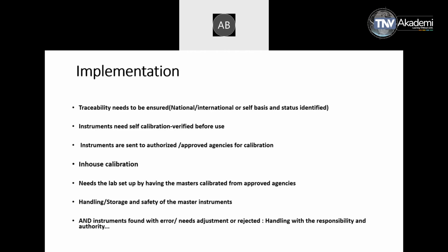Once we start doing calibration in-house, the training of the team again comes into the picture. They need to be trained to do effective, good and correct in-house calibrations of the instruments and machines. Then there is how to handle, store and keep safe the master instrument. This is very important, because master instruments which are calibrated from an outside agency, national or international, approved or linked to that, have to be handled very carefully, because if their accuracy is not kept under control, then when we are doing in-house calibration, our instruments will not be accurately calibrated.